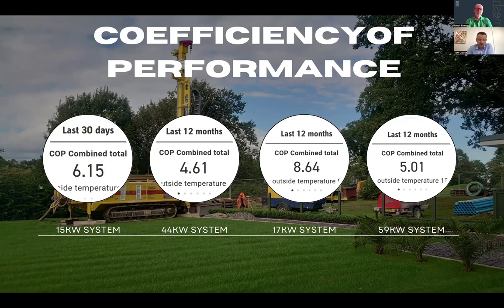Temperature in the cylinder is set to 52. It will drop, let's say, to 47, which is a delta T of 5. You can say, okay, now we've dropped by 5 degrees, I will top up the hot water cylinder to 52, and it will then wait and constantly monitor the temperature in those two tanks and the outside temperature. Overnight, the heat curve will go slightly higher, so it will generate a bit more. And the best systems are working being heated all the time.